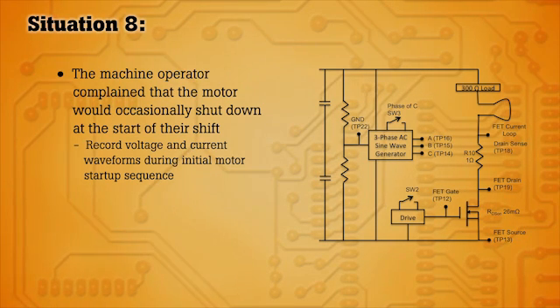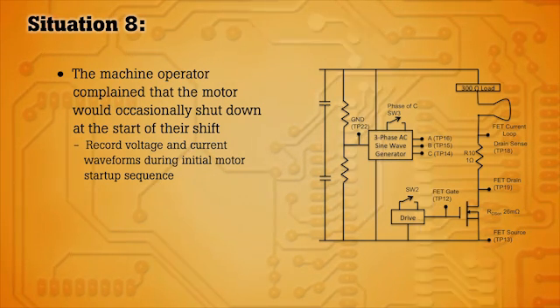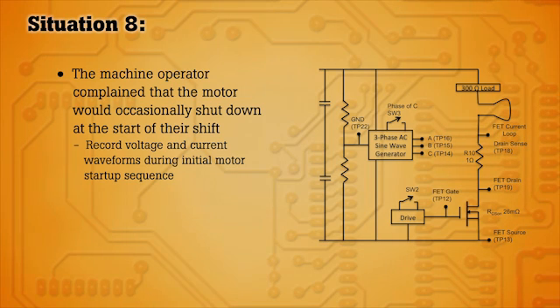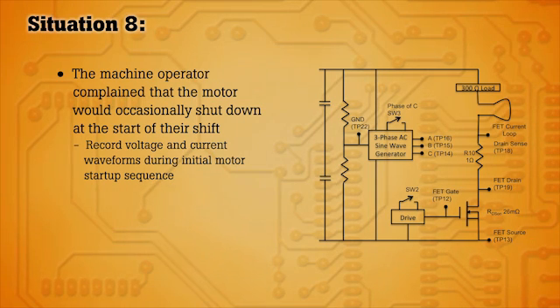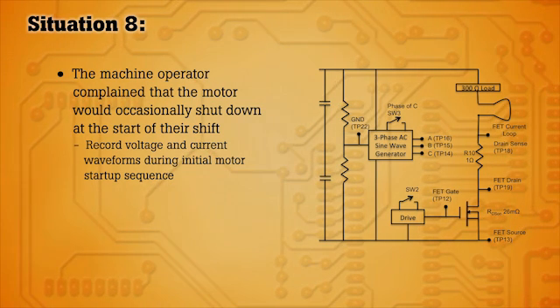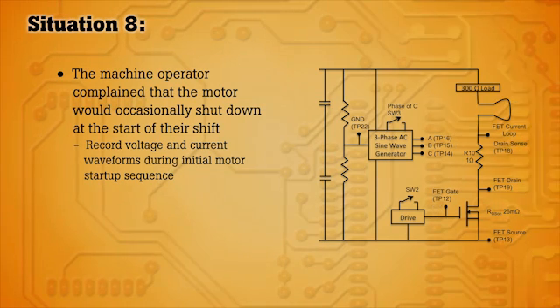The events behind this type of problem may be random in nature and difficult to capture. In order to ascertain why the machine is shutting down, we'd have to capture multiple parameters at the instant it shuts down in order to diagnose the root of the failure.